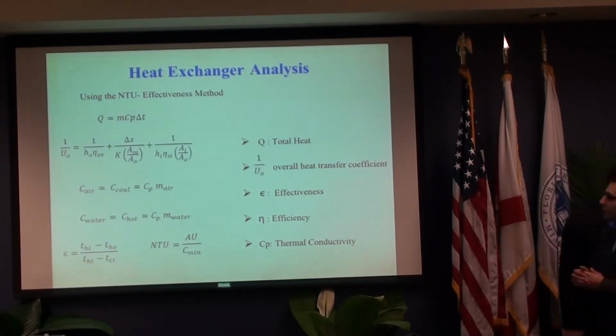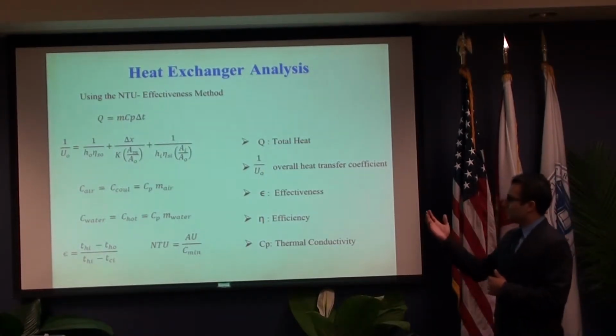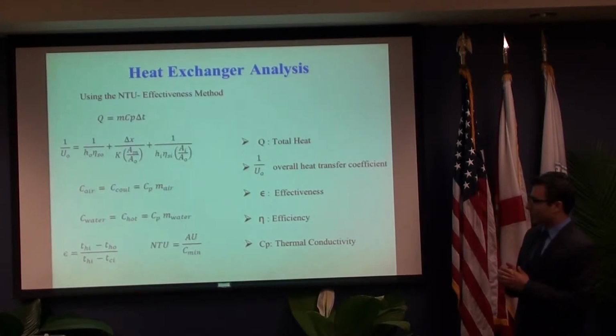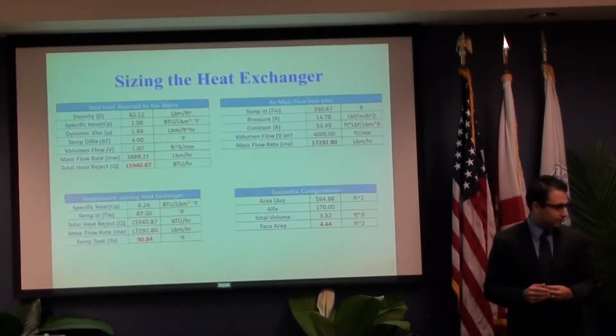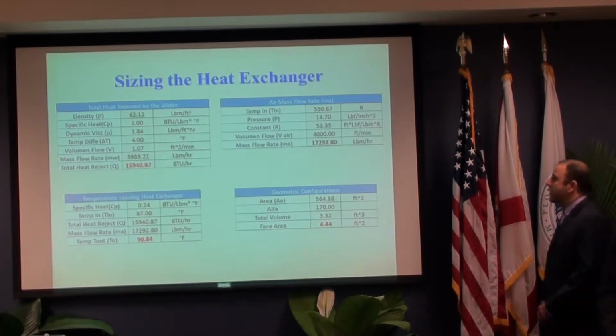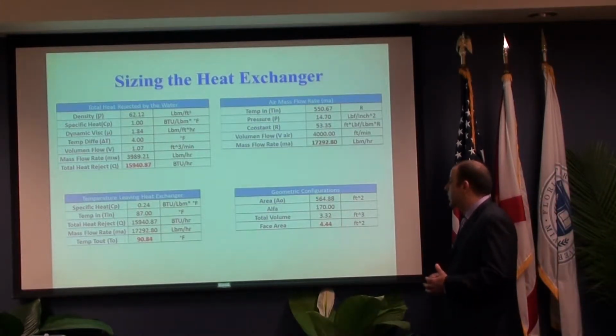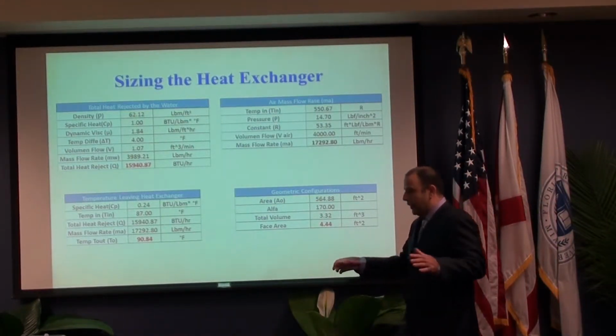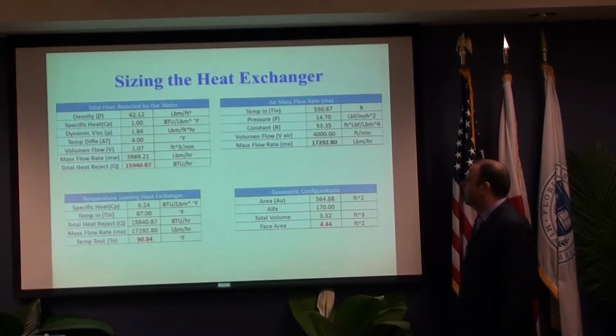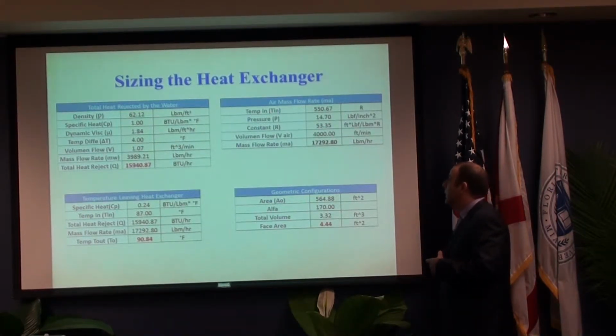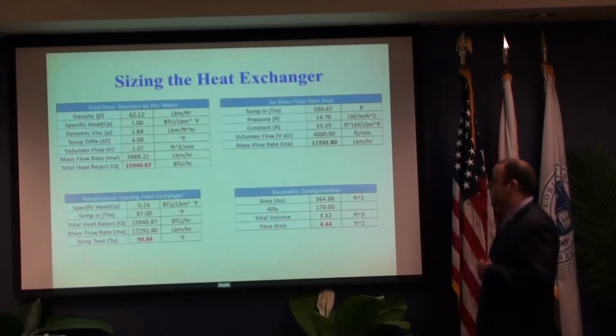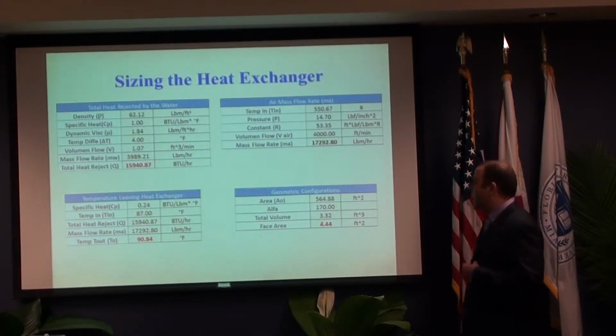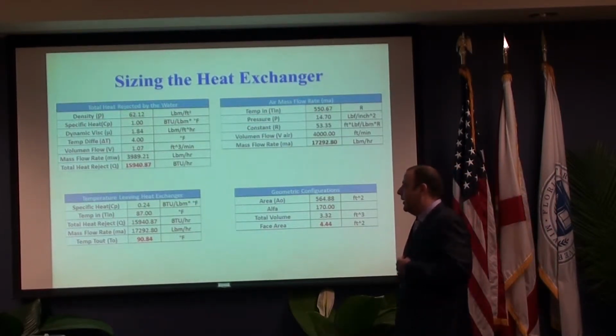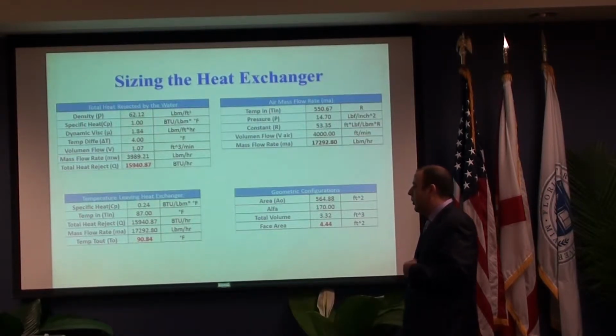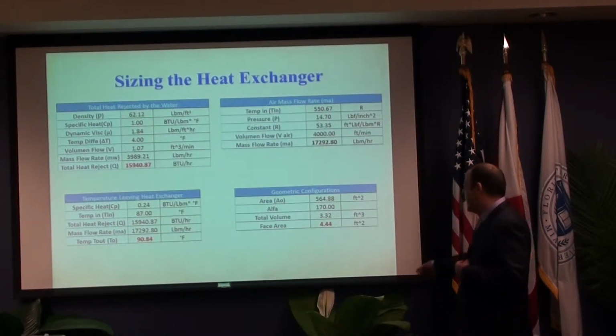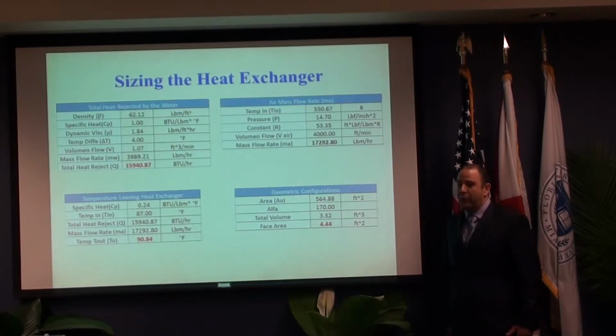To solve this problem, we used the NTU effectiveness method, and these are some examples of the equations that we use. The objective of this calculation is to find the face area that we need in order to size the heat exchanger. So we started with the total heat rejected by the water, then the mass flow, the temperature leaving the heat exchanger. The temperature going in is 87 degrees Fahrenheit and going out at 90.84. And finally, this value, 4.44.